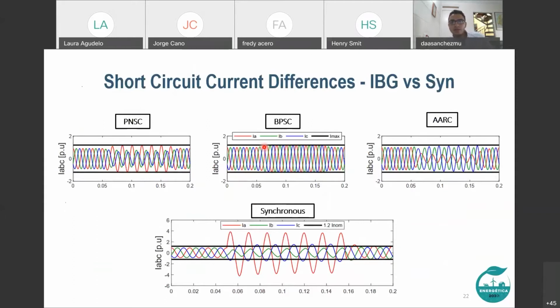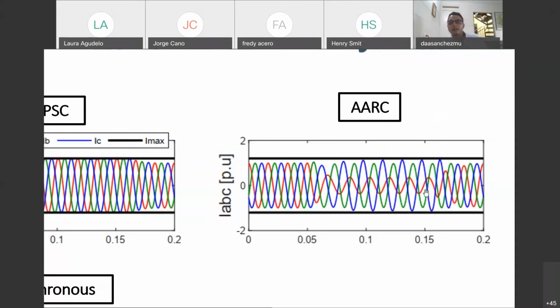From the last slide, we have different control strategy impacts, but look at this. All these IBG strategies are still different compared with a conventional synchronous machine. So traditional schemes adjusted for protecting conventional synchronous systems will surely be affected. As a particular fact, in conventional generation the faulted phase current is the biggest one. But in the AARC strategy, the faulted phase current is the smallest one. So it's very particular.